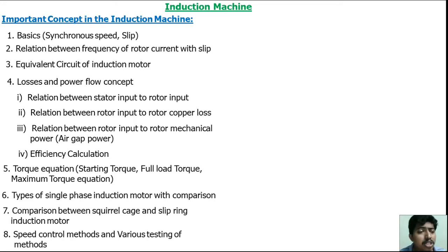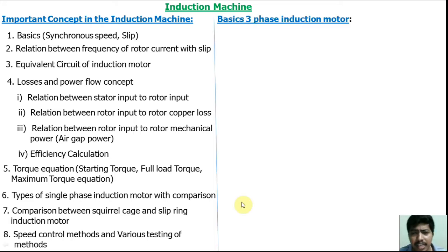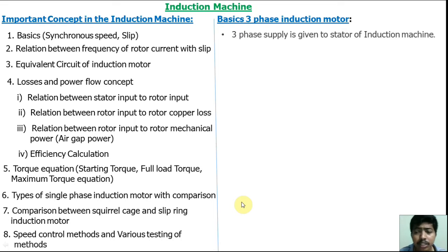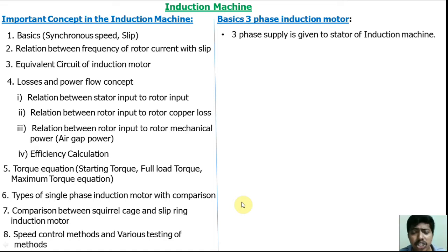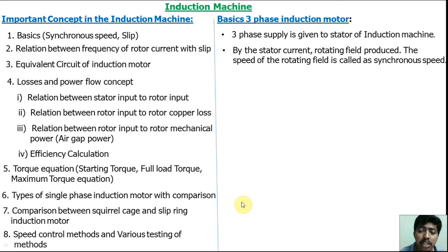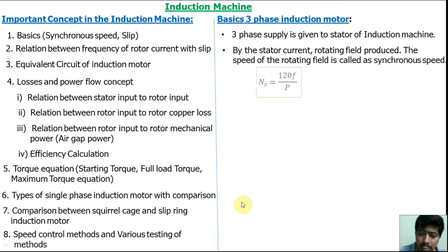In this part one video, we discuss the basics of a three-phase induction machine. The three-phase supply is given to the stator. In the stator there are three coils, each separated by 120 degrees. When three-phase supply is given to the stator winding, a rotating field is produced. The speed of the rotating field is called the synchronous speed. The relation is: Ns (synchronous speed) = 120f / P.